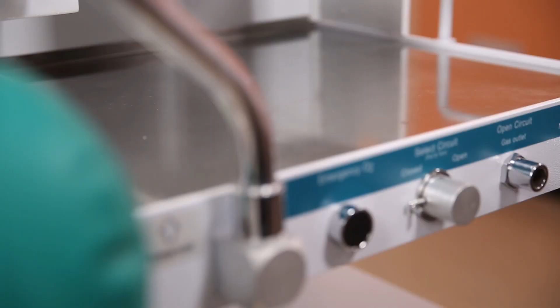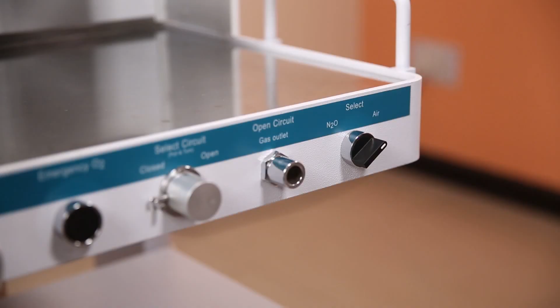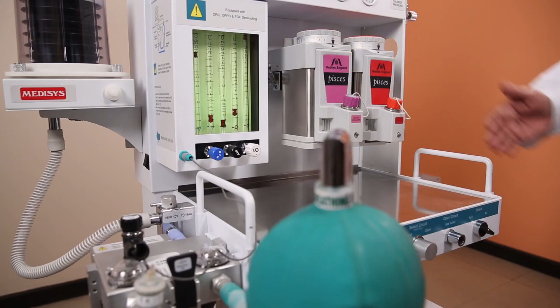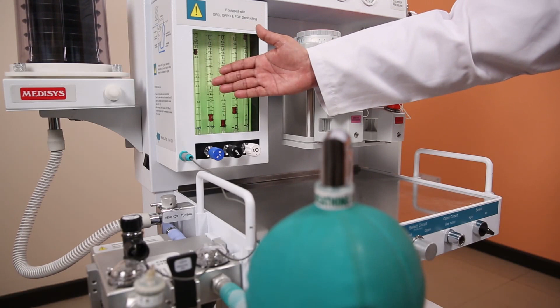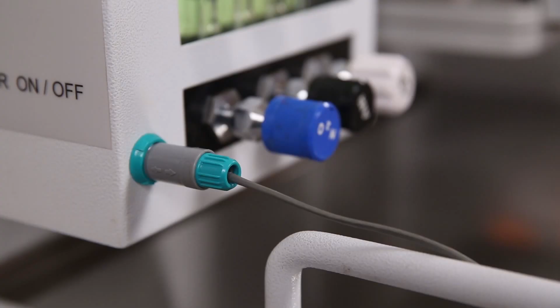Another very interesting safety feature in this machine is the air nitrous oxide lock. By this we mean that if nitrous oxide is running, air cannot be put in, and while you want to use air, nitrous oxide will not run. By just simply flicking a switch, that means nitrous oxide and air will never simultaneously run. This is a big safety factor.